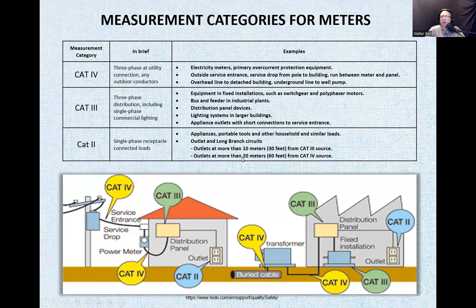Now, at more than 20 meters, 60 feet, or you can measure also if you're further than 20 meters or 60 feet from the Cat4 source, which is anything that's outside. You see here, here's a transformer, that's a Cat4 source. Outside, here is the meter. Here's the service that's connected to the house. It is outside of your house. As soon as it's outside, it automatically becomes Cat4. So that's when we have long branch and short branch terminology.